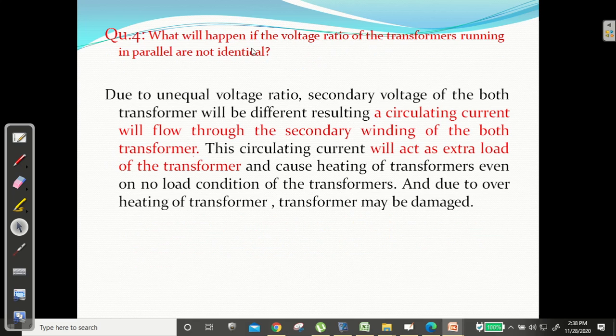Question number 4. What will happen if the voltage ratio of the transformers running in parallel are not identical? Suppose the voltage ratio is a bit different, primary of both is 440 volts, secondary is 110, second transformer primary is 440 volts, secondary is 108, phase sequence same, everything is same, but because of this 2 volt difference here, clear? So circulating current can flow. Okay, so due to unequal voltage ratio, secondary voltage of both the transformers will be different, resulting in circulating current flowing through the secondary winding of both transformers.